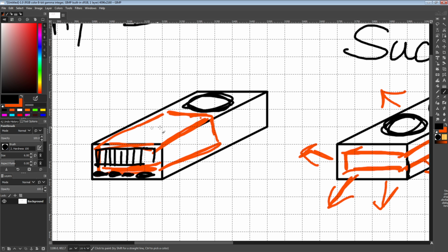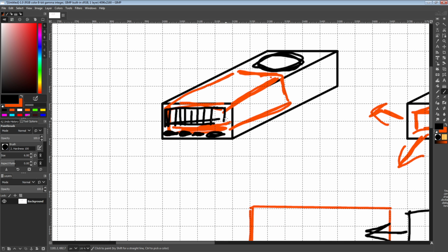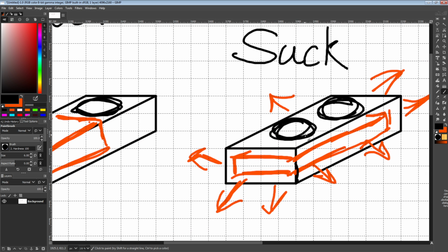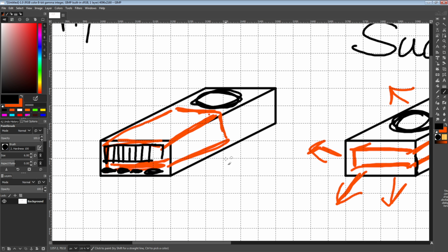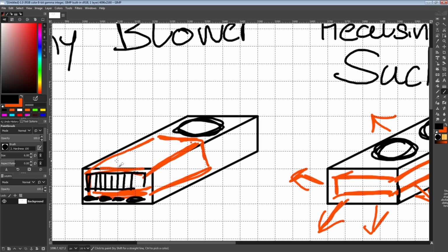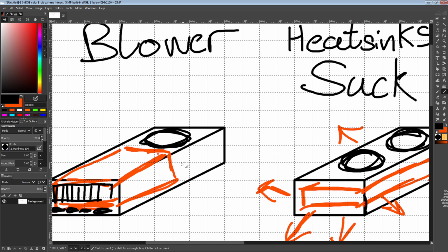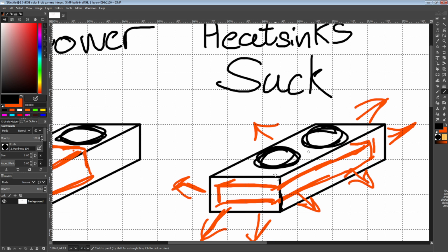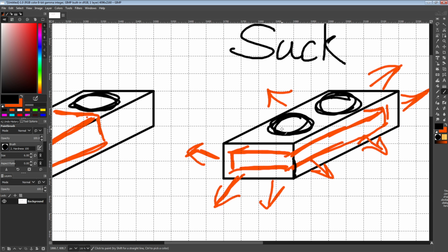This sucks because you're trying to cram a lot of air through a very small opening instead of the same amount of air through a much bigger opening. Air has a fixed amount of cooling capacity it offers, so if you have a similar size heat exchanger, the only way to get more cooling out of it is to shove more air through it. There's nothing else you can do, and that's where open air cards have their first big advantage.